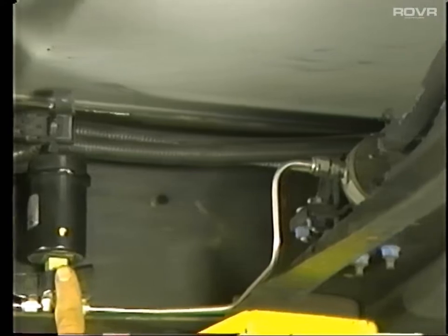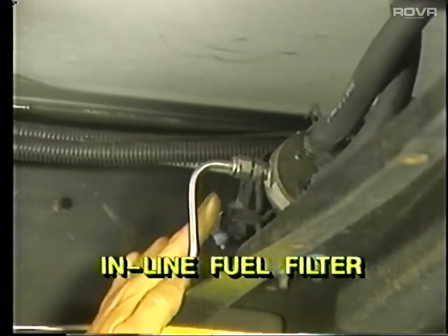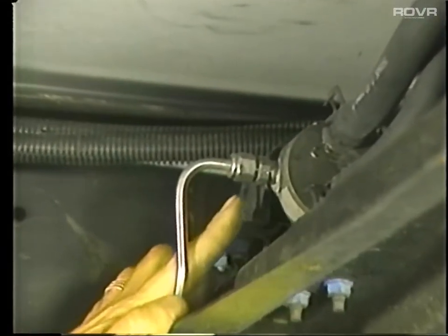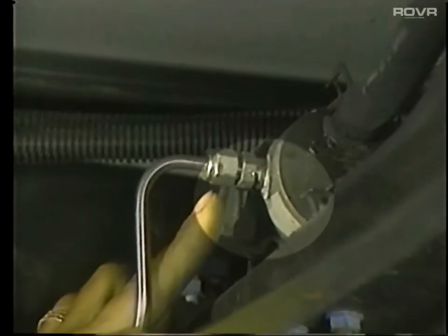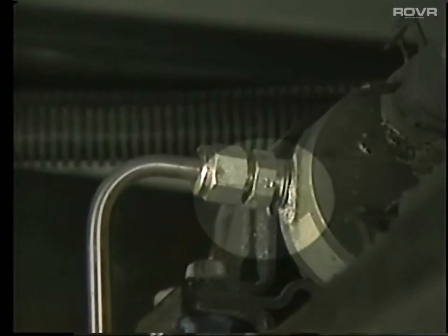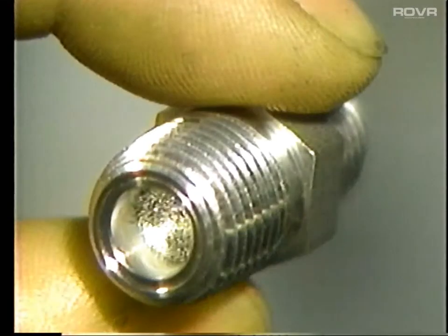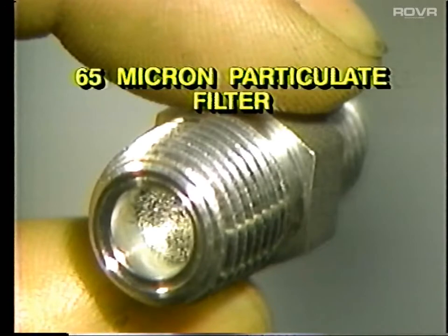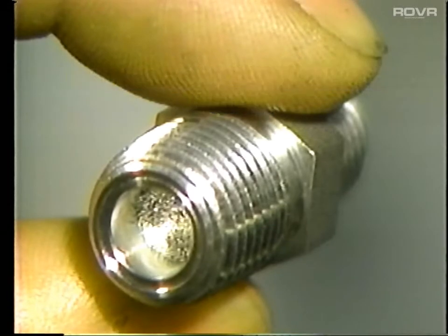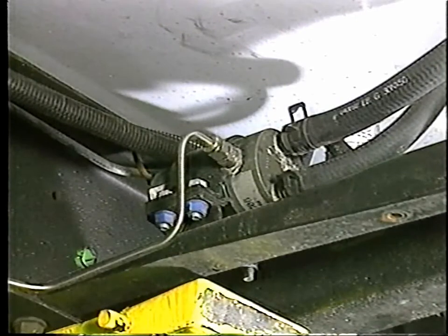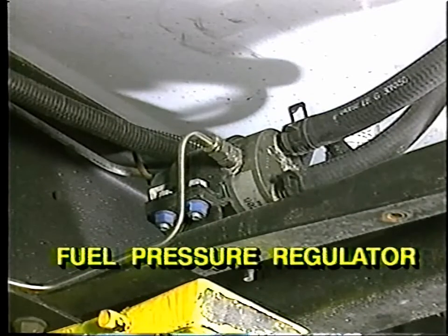An item that was not covered in the earlier video is the inline fuel filter. You'll recognize it because there was a small arrow stamped on it. If you don't find an arrow, it isn't a filter but merely a fitting. If you find one, replace it immediately with a filter. The arrow must be pointed backward toward the fuel tanks. This is a 65 micron particulate filter that protects the system from contaminants that may be carried in the natural gas. If there is a heart of the entire natural gas fuel system, this is it: the fuel pressure regulator.